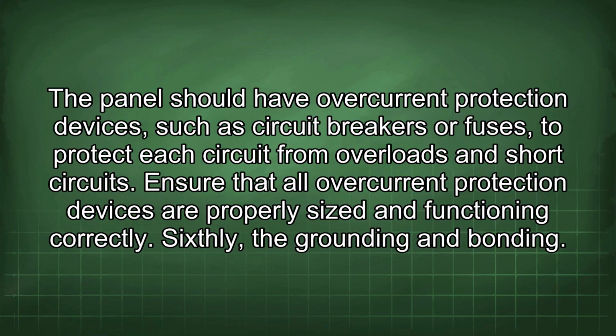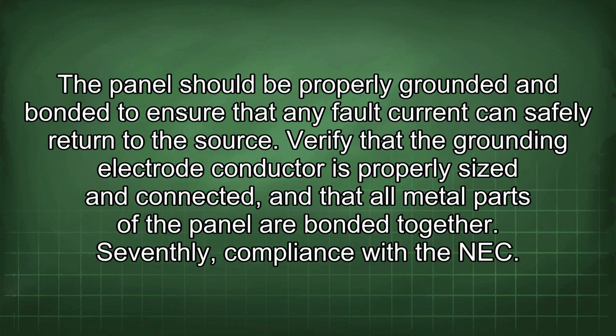Sixthly, the grounding and bonding. The panel should be properly grounded and bonded to ensure that any fault current can safely return to the source. Verify that the grounding electrode conductor is properly sized and connected, and that all metal parts of the panel are bonded together.